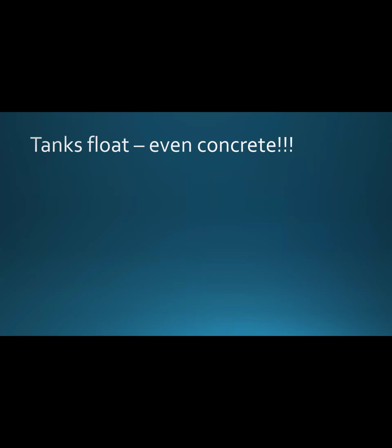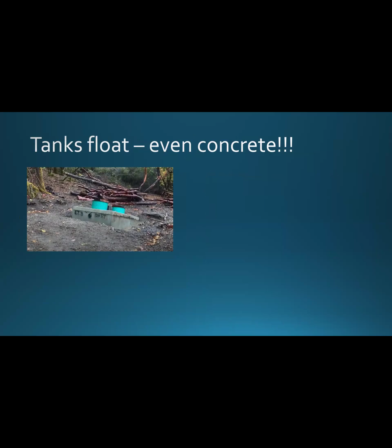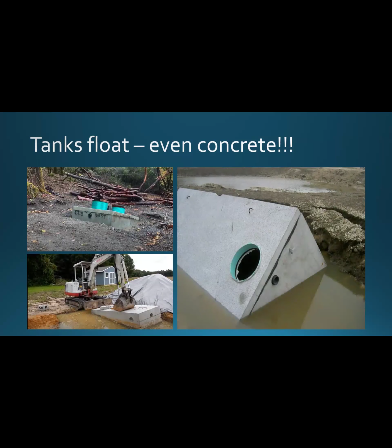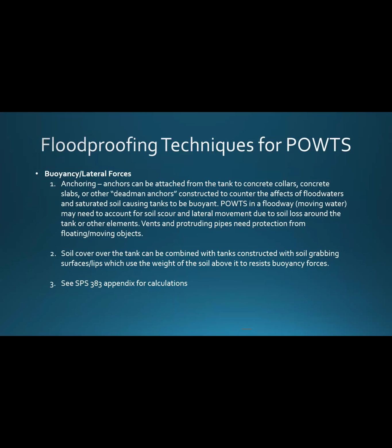Also, if we're in an area that's flooded, tanks could float, even concrete. Here's a bunch of different pictures where we've had flooding and saturated soils. The tanks will pop up out of the ground. Some people think it's really hard to imagine that concrete tanks float, but battleships float, and they're made of steel. If we're displacing more water than the weight of the tank, they're going to come up and out of the ground on us. So we've got to make sure that we're keeping them in the ground and anchoring them.